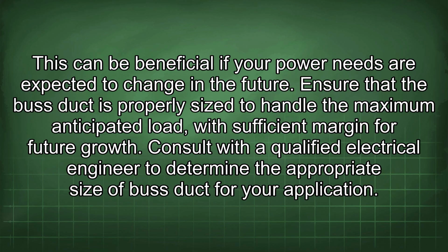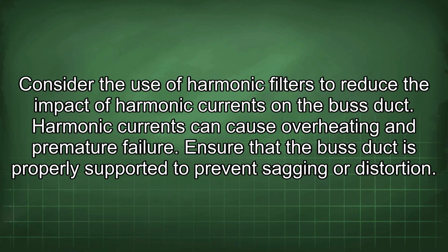Ensure that the bus duct is properly sized to handle the maximum anticipated load, with sufficient margin for future growth. Consult with a qualified electrical engineer to determine the appropriate size of bus duct for your application. Consider the use of harmonic filters to reduce the impact of harmonic currents on the bus duct. Harmonic currents can cause overheating and premature failure.